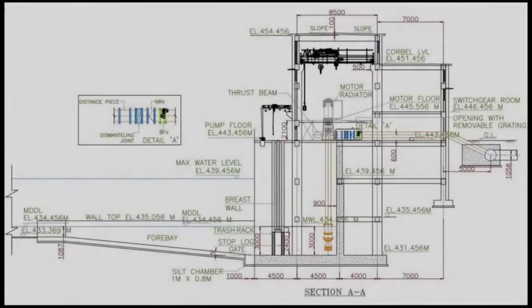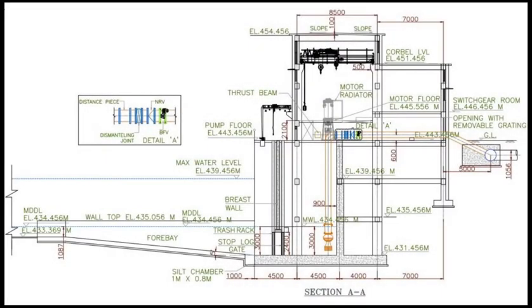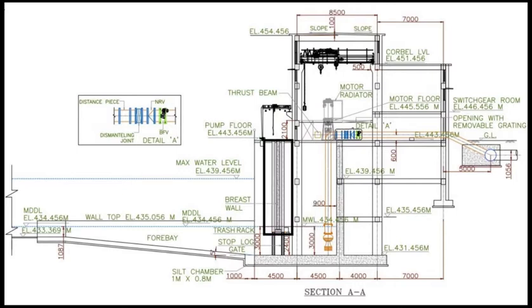The model study is proposed for water level at minimum drawdown level, that is MDDL, and for MDDL plus 3 meter level. The MDDL level is 434.456 meters, and MDDL plus 3 meter is 437.456 meters. The pump bay consists of the bell mouth, suction pipe, and breast wall arrangements.